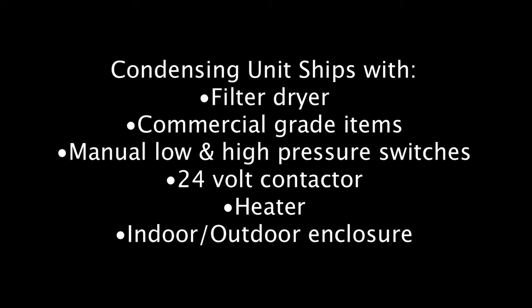It has commercial grade items such as a sight glass for observing the levels of refrigerant, manual reset high pressure switches, low pressure switches to protect the compressor and the refrigeration circuit, 24 volt contactor for control of the fan coil unit as we talked about, crankcase heater, and as standard fare an outdoor enclosure which can be used for mounting the system outdoors, but as I had mentioned, it can certainly be used for mounting indoors as well. It doesn't necessarily have to be mounted outdoors. The enclosure is standard where others offer that as an option.